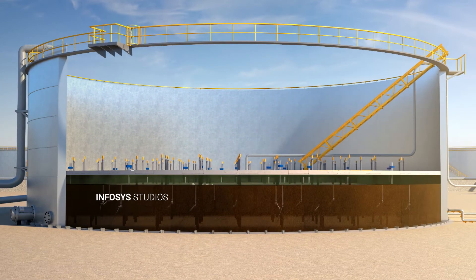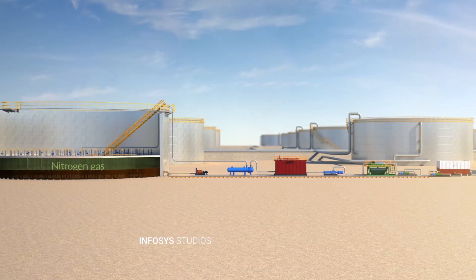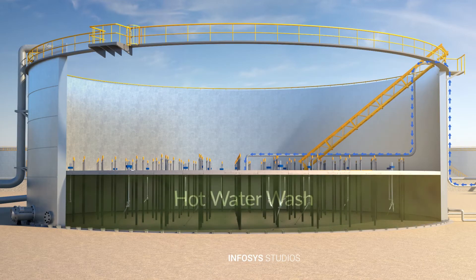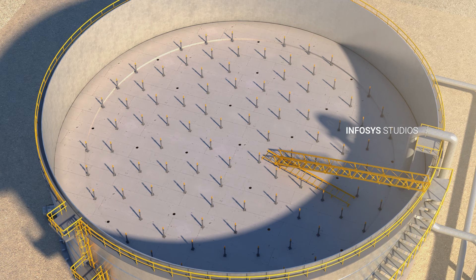As the level of sludge is lowered, nitrogen is introduced to fill the void space. Finally, the tank receives a hot water wash before venting the tank to atmosphere. The final step is to reinstall the tank legs and use vacuum to remove residual liquids.